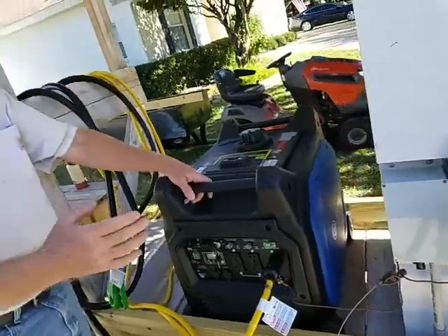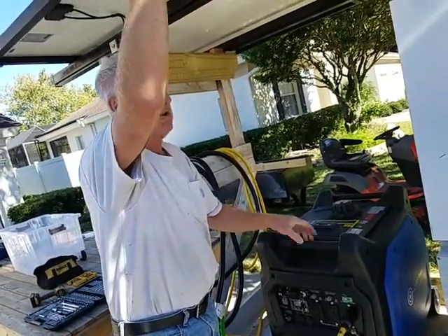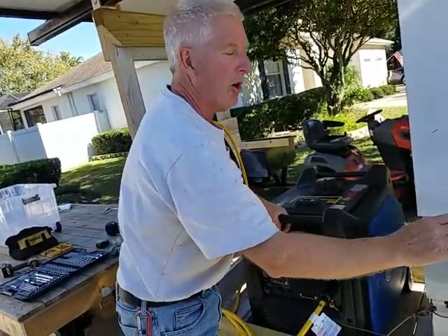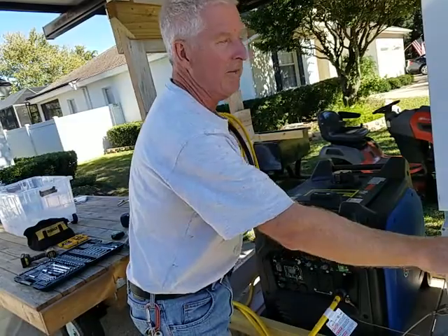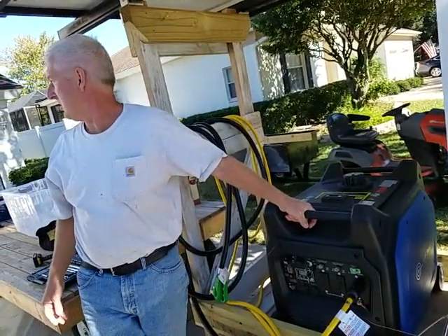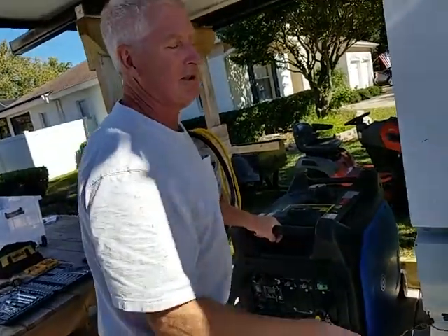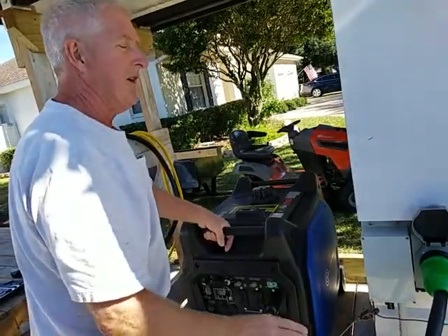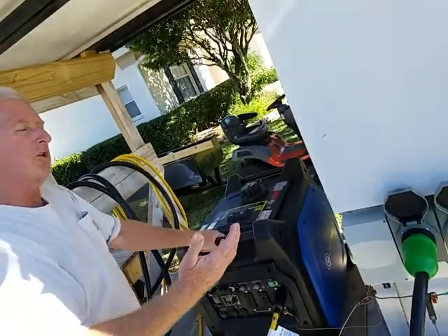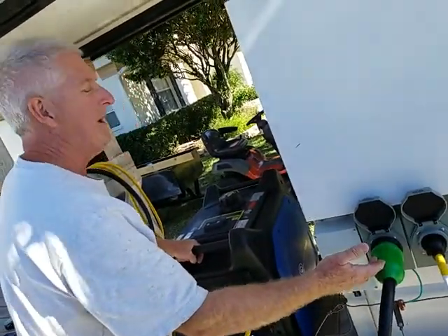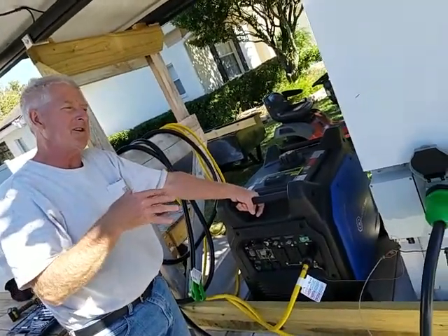We can even set up priority. We can say our priority for power would be solar first. If solar is not enough to charge the battery, we want to call on the generator. And if the generator can't supply the power that we need, we're going to call on the grid. But we could change the sequence, and again, this is programming. We could say we want solar priority. If solar's not enough, we could go to the grid, and then the generator. So those priorities will be established for us based on our intended use.